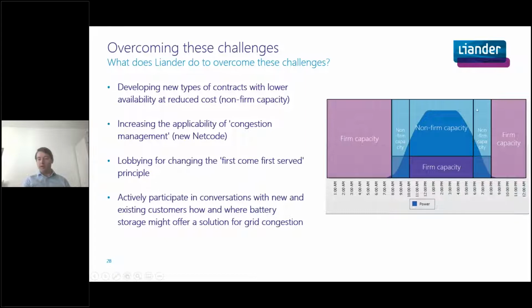So you can only discharge your battery, or not use it, at those times. During the day, when there's solar production, you can charge it, but not discharge the battery up to the limit of the grid connection. Outside those hours, at night, you have unlimited capacity — there's a lot of capacity left during other hours where you can actually deliver ancillary services, for instance. So we think this type of contract might be a good solution for integrating storage and other flexible assets into solar energy parks.